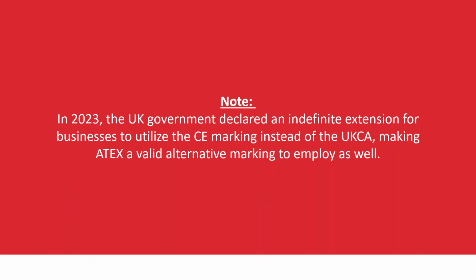Now, you may have noticed in that last slide, I used the word "was" more than once. In 2023, the government declared an indefinite extension for businesses to utilise the CE marking instead of using the UKCA, making ATEX a valid alternative marking to employ as well. So basically, any product that has an ATEX mark on it can be used within the UK, but also always look out for UKCA or UKEX and ATEX to be on the safe side.